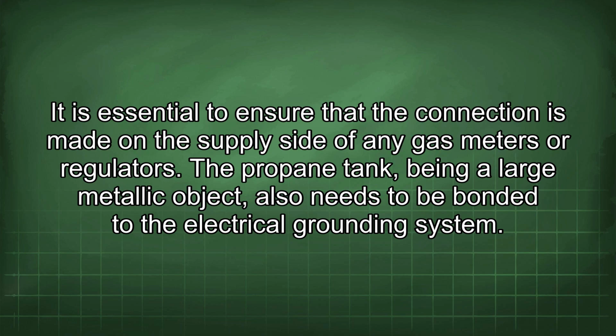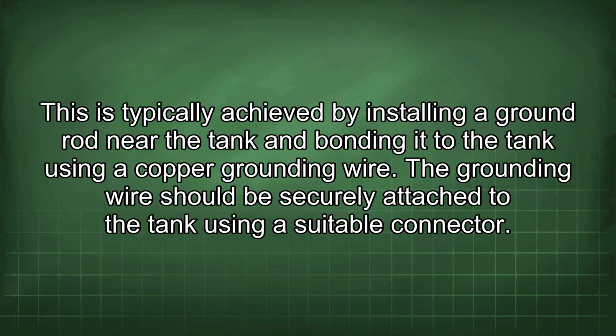The propane tank, being a large metallic object, also needs to be bonded to the electrical grounding system. This is typically achieved by installing a ground rod near the tank and bonding it to the tank using a copper grounding wire. The grounding wire should be securely attached to the tank using a suitable connector.